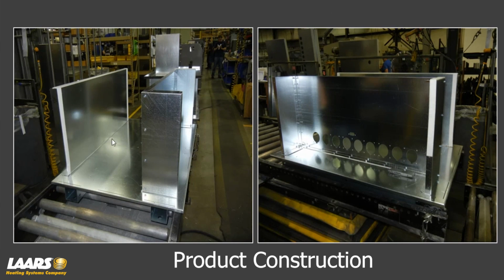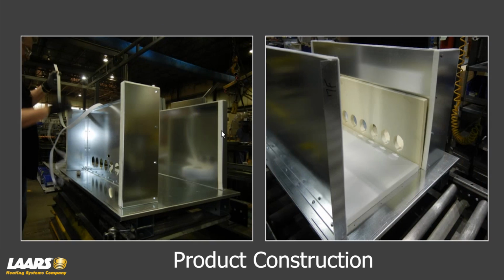We start with the base and put the back wall on. Next, the front wall. The right-hand image here is showing the front wall with the openings for your burners, and we'll see all this being built. Next, they'll start by adding some insulation and the refractory block for your combustion chamber. And again, these orifices or openings here are where your burners will come through.